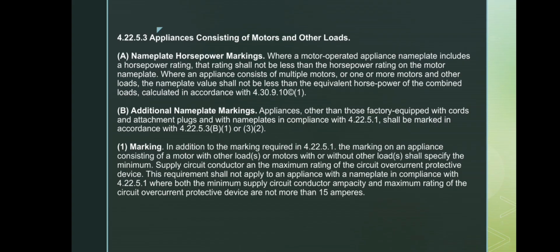First, under nameplate horsepower markings. If an appliance has a motor and its nameplate shows a horsepower rating, the rating cannot be lower than the horsepower shown on the motor itself. If the appliance has multiple motors or motors combined with other loads, the nameplate must show the total equivalent horsepower of all loads combined, calculated as required by the code.